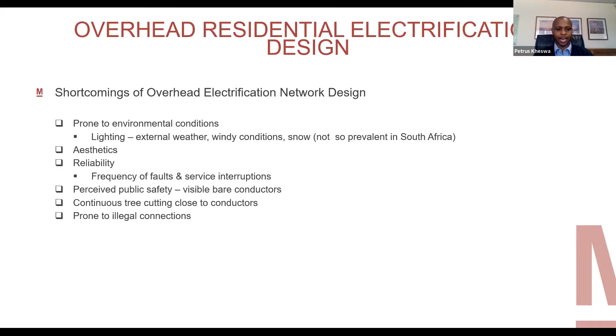This happens in most cases in urban areas where you have overhead networks. There has to be continuous cutting of trees close to the conductors to ensure that faults on the network are reduced, because you don't want trees closer to the conductors, as that leads to service interruptions. In some instances, it's also prone to illegal connections, since people perceive overhead networks as easier to illegally connect to.